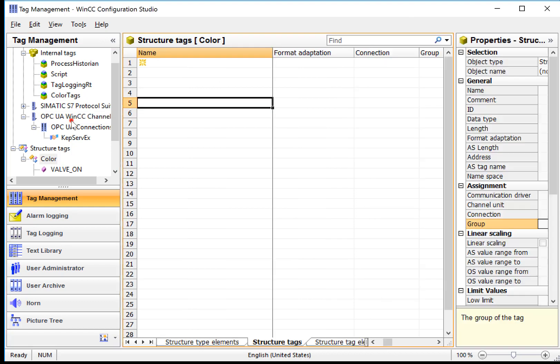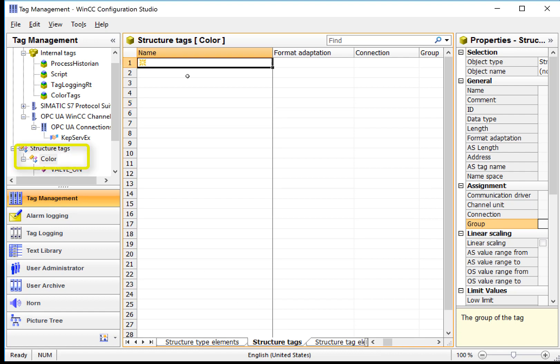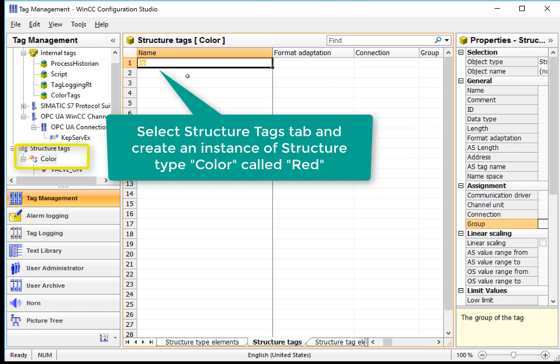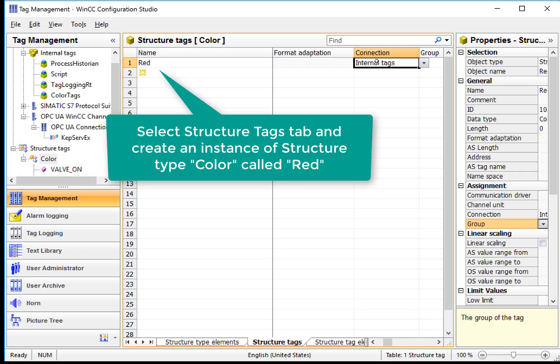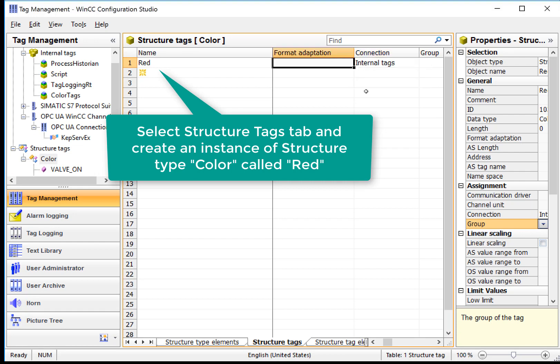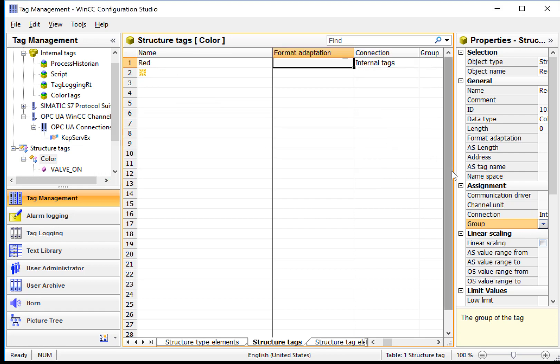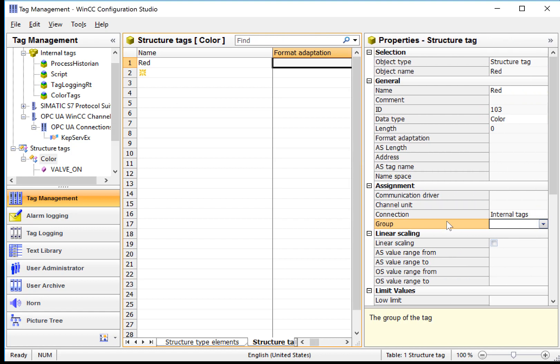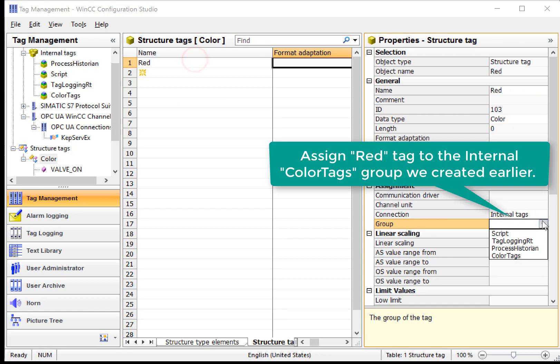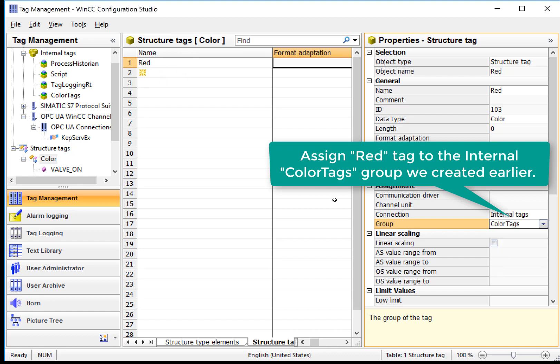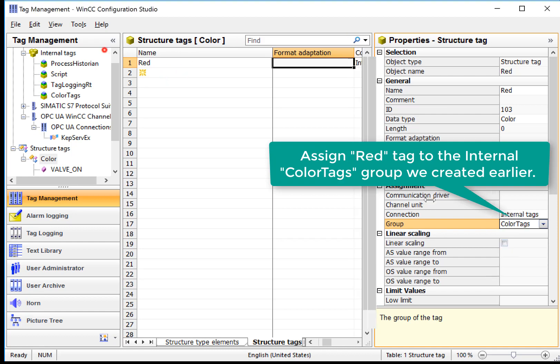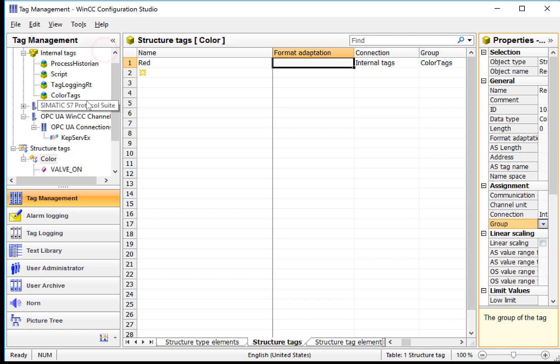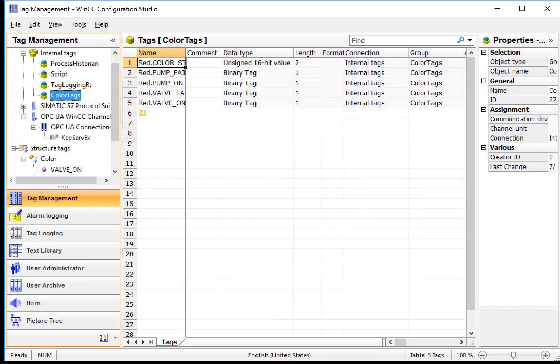So on the Structure Tags tab, you can see that this is a list, which is empty right now, of instances of the color structure type. So I can just highlight the first item, create a structure tag called red. And it should be assigned to our Internal Tags connection. And then if I do that and pull out the Details screen, then I can assign it directly to our Color Tags group.